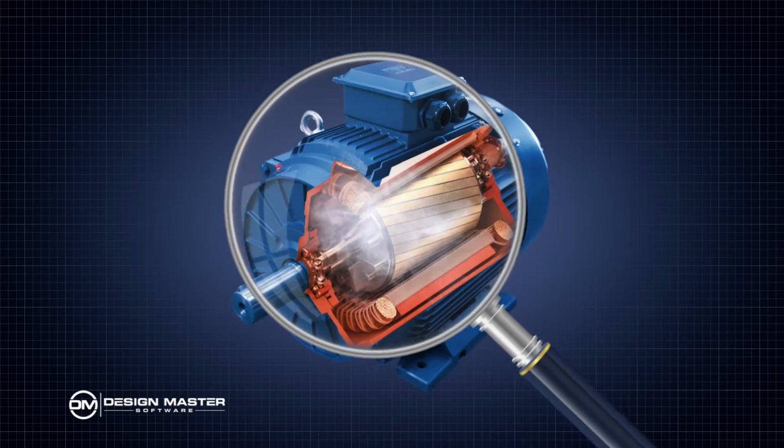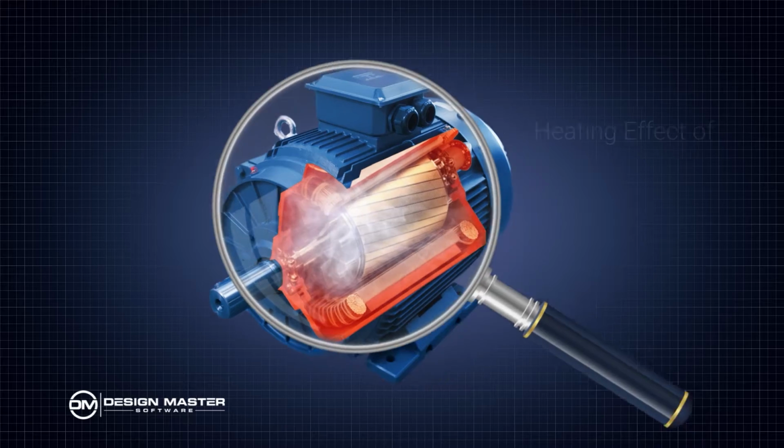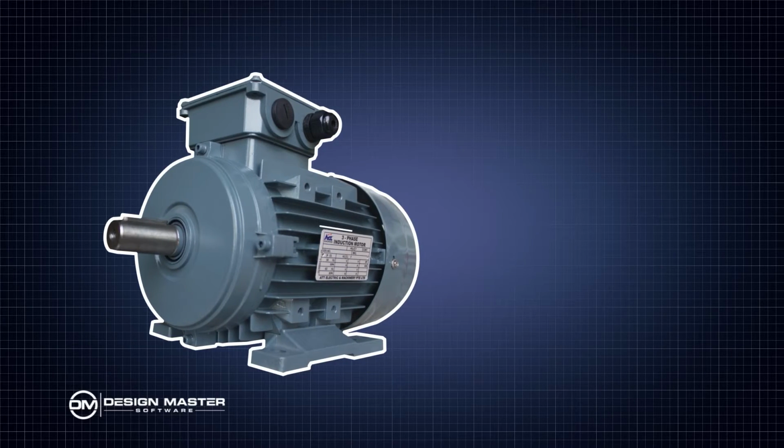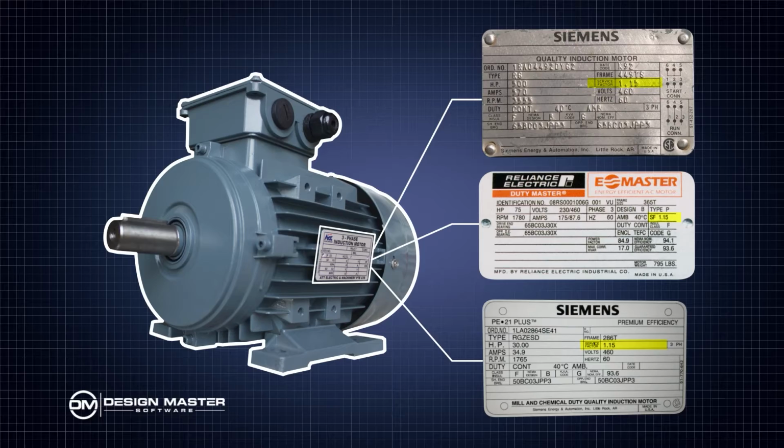And of course, this is all based on not stalling. You can't oversaturate the magnetic elements of the motor and stall. What happens when the loads increase beyond the rated horsepower? Well, first of all, the motor gets warmer, just simply gets hotter, because you get I squared R, the heating effect in the motor. And you're allowed to go over the rated current or the rated horsepower a little bit on some motors. There's a term called the service factor, and that will be printed on the nameplate. And a typical service factor is 15%. So you can take a motor and run it 15%.